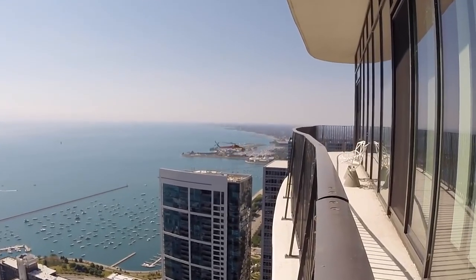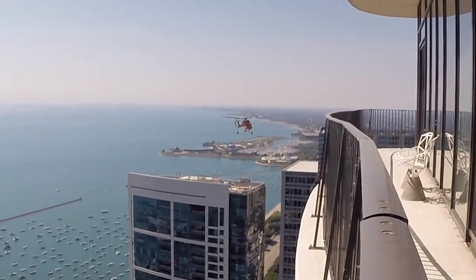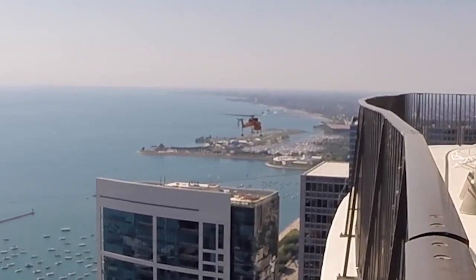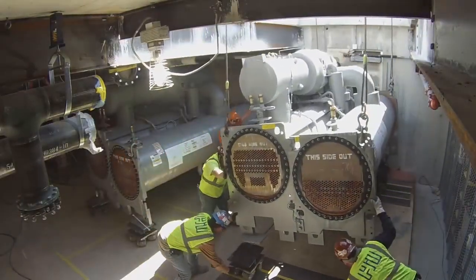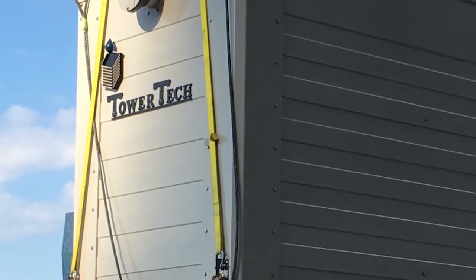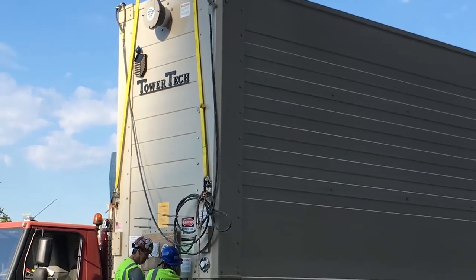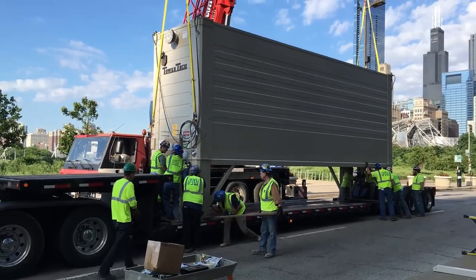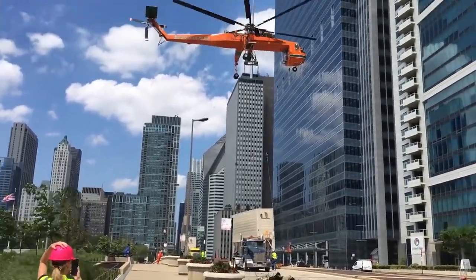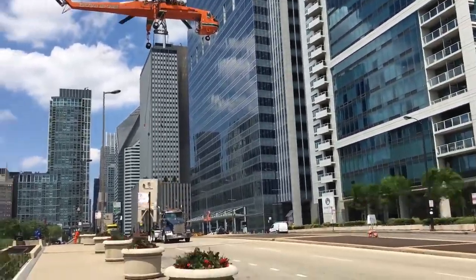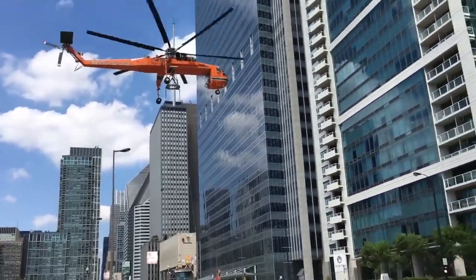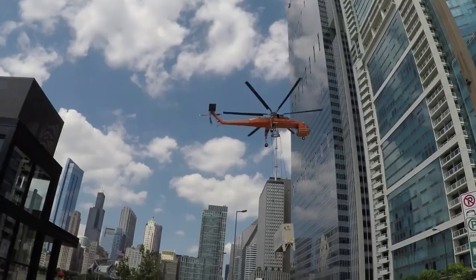Lifting chillers near the maximum capacity of the helicopter sounds very stressful, and it is, but what was even more stressful was watching the helicopter pick up the cooling towers. The cooling towers are about half the weight of the chillers, but substantially larger, and when you have hurricane force winds coming down off that helicopter, bouncing off the building and pushing against the cooling tower, that tower starts to move, and it's going up 64 floors.